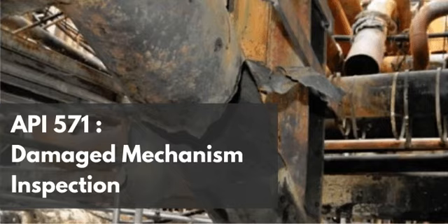We talked about how high-strength steel is dangerous, but for carbon steels with a tensile strength not greater than 70 ksi, there is an absolute mitigation: post-weld heat treatment. Post-weld heat treatment, or PWHT, is the ultimate engineering countermeasure for carbon steel in ammonia service. We spent a lot of time discussing how the rapid cooling of a weld locks massive residual tensile stress into the atomic lattice of the HAZ. Right. PWHT is the process of safely erasing that stress.